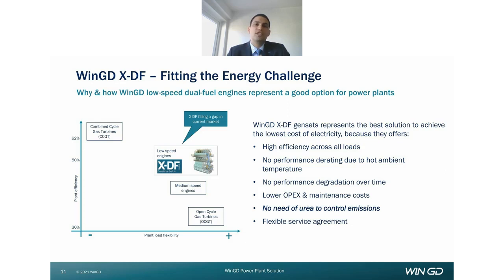The key enablers to achieve this target are, in first place, the high efficiency we provide across all loads. As I will present in a couple of minutes, at low load, our efficiency is still above 45%. Compared to gas turbines or medium speed genset, we have lower maintenance cost. Compared to the medium speed genset, one key advantage that we provide is the fact that we do not require any after-treatment solutions such as SCR system and a CO catalyst to operate our genset within the European regulation in terms of NOx and CO emissions. This means we do not need urea to control the NOx emission, and this has a positive impact on the operating cost of the power plant.